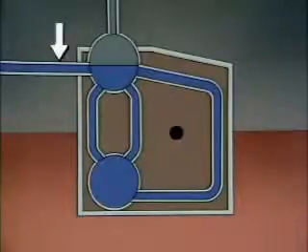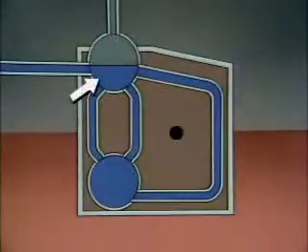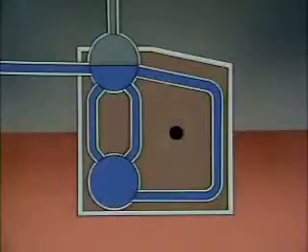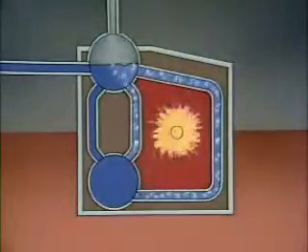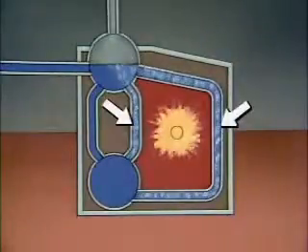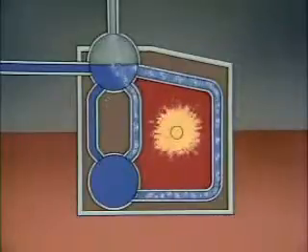The boiler also has a feed water inlet and a steam outlet. The water tubes and lower drum are filled with water, while the steam drum is only partially filled, leaving space for steam to collect. As combustion occurs, the water tubes surrounding the combustion area heat up, and as heat is transferred to the water in these tubes, the water becomes less dense and lighter than the cooler water elsewhere in the boiler.